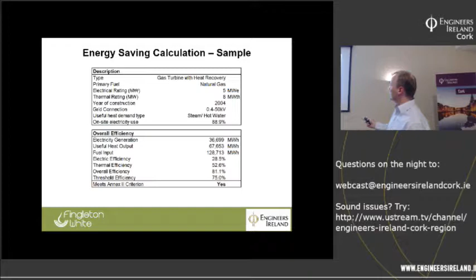And it's the same with the voltage. Depending on what grid connection voltage you're connected at, they've got different correction factors for the reference electrical efficiency. And then depending on whether you're exporting or using it on site, there's a separate correction factor for that as well. So that's the CHP. Then you have your production stats here: the electricity output, the useful heat output, and the fuel input. And then the spreadsheet takes these values and does a check. So if your overall efficiency is above the threshold, which is 75%, then all of the electricity generated in a gas turbine CHP qualifies as electricity from high efficiency CHP.